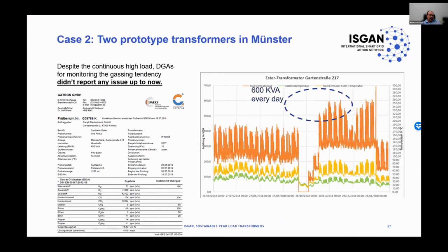So this is exactly how the sustainable peak load can work, and the utility is testing the transformer not only as a duty cycle, but even as the composition inside the material and lifetime of the transformer, performing DGA analysis continuously every year for monitoring the status of the transformer. Obviously, after 4 years, if we are speaking about this case, the transformer is still running in a perfect way, and the customer is very satisfied about this.